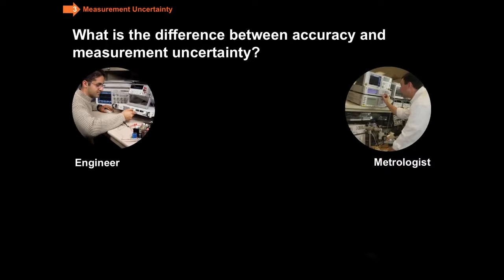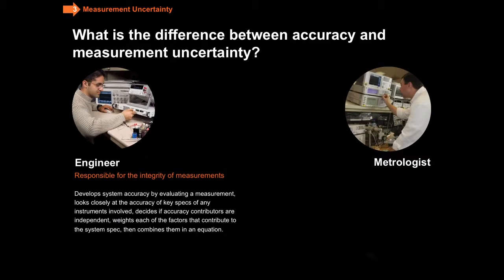What I'd like to do is just quickly draw a distinction between accuracy and measurement uncertainty. Let's take a look at how does a metrologist versus an engineer examine the accuracy of a measurement. So an engineer who's responsible for measurements will develop a system accuracy by evaluating a measurement. They're going to look closely at the accuracy of any key specs that matter, decide if those individual error contributors are independent, and come up with some way of weighting each of the factors and combining them into an equation in an appropriate fashion.